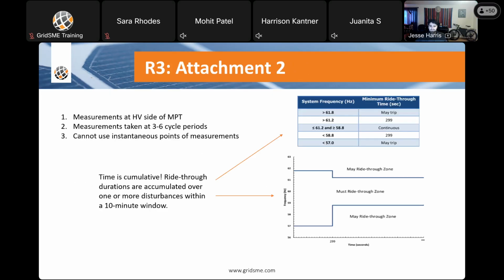So here's attachment 2, which defines the must ride through and may ride through zones for requirement R3. Again, measurements at the HV side of the MPT must be taken at 3-6 cycle periods. So you can't use instantaneous points of measurement. And time is cumulative. Ride-through durations are accumulated over 1 or more disturbances within a 10-minute window. So this window will shift. And I forgot to mention actually that for the voltage, it's the same, except it's a 10-second window.